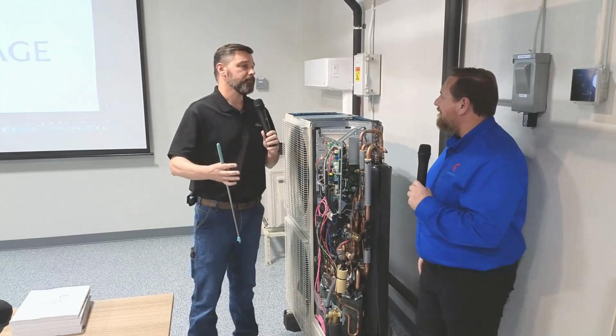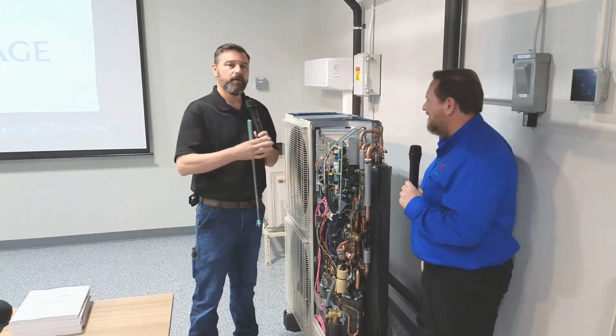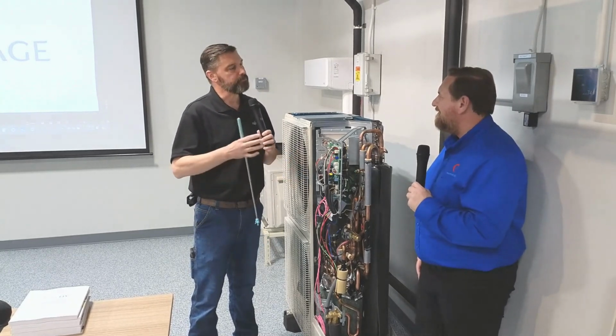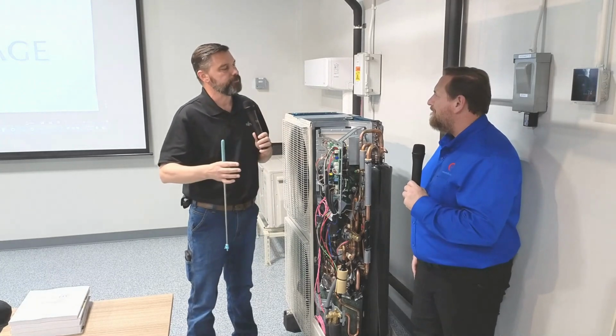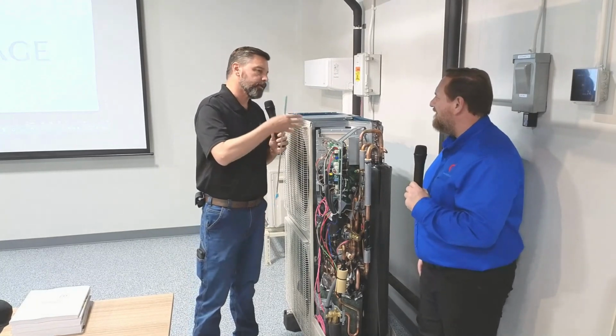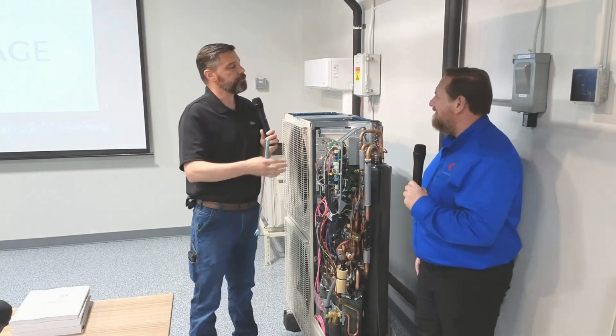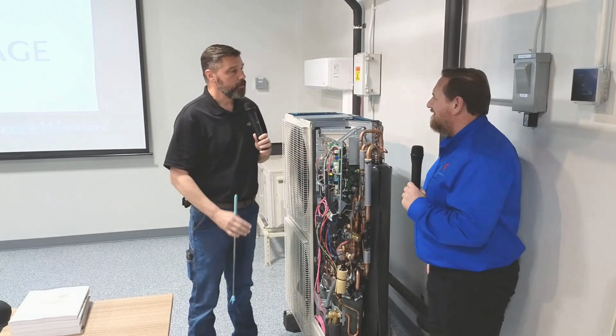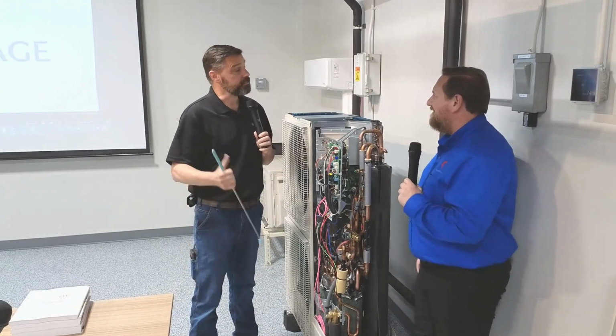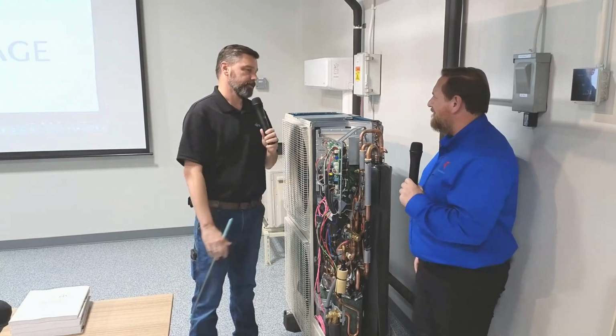We've got our service tool software we can hook up to the system, letting us see all the temperatures and pressures and watch the flow of refrigerant through the system. This lets us understand what's going on inside, so we can determine whether the system's operating properly or if adjustments are needed, either to the installation or the operation.